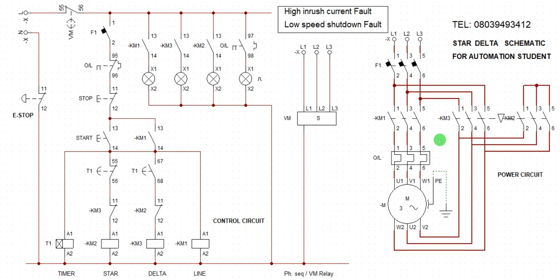Let us discuss the conventional operation sequence of star-delta. When you initiate the operation, the line contactor (main contactor) and the star contactor both get activated simultaneously. After a few seconds — about five seconds — the star contactor gets de-energized and the delta contactor gets energized. Low speed is when the motor is running on star; high speed is when it's running on delta. When star is disengaged and delta is engaged, the motor goes to high speed.